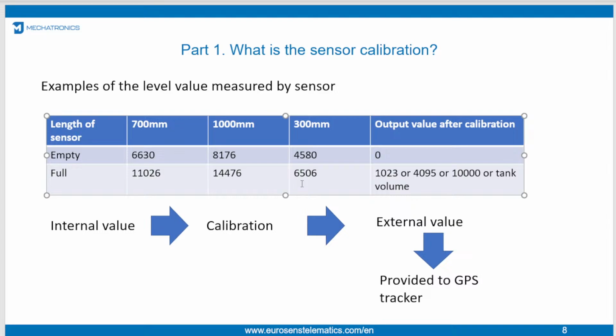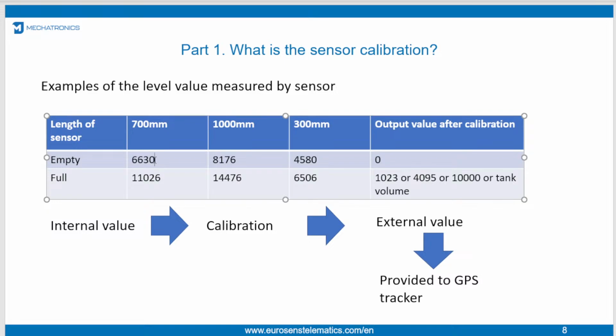And so that's why we have an internal sensor value and an external sensor value. The internal value is the result of measurement, this one, and the external is what the sensor sends to your GPS tracking device. And what's tank calibration? We just make relations between them. We teach the sensor that this value is going to be 0, and for this value, please give us, for full tank, we want to see 1023, for example, or it can be any value like 10,000. Please give us this exact external value on a full tank.